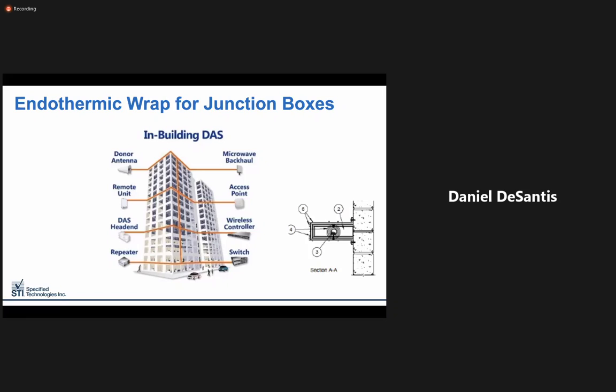This could be part of a DAS. This could be a part of an emergency DAS system oriented against the CMU block wall. Using endothermic wrap, this box is now protected for a 2-hour fire resistance rating. You'll notice in this orientation against the CMU wall, the endothermic wrap is fastened directly to the CMU substrate. Since the box is mounted directly to the wall, this saves space on the project without sacrificing any of the circuit integrity requirements.